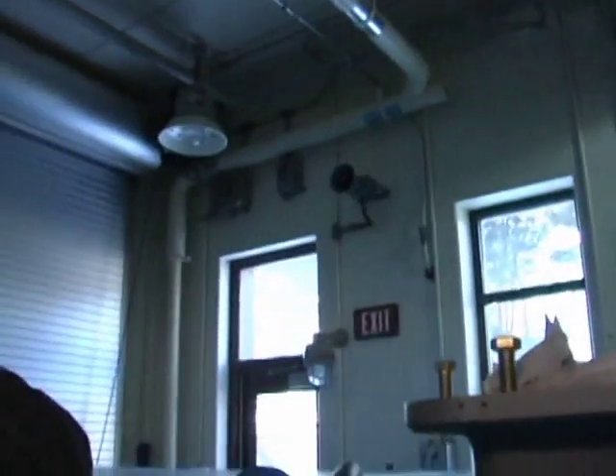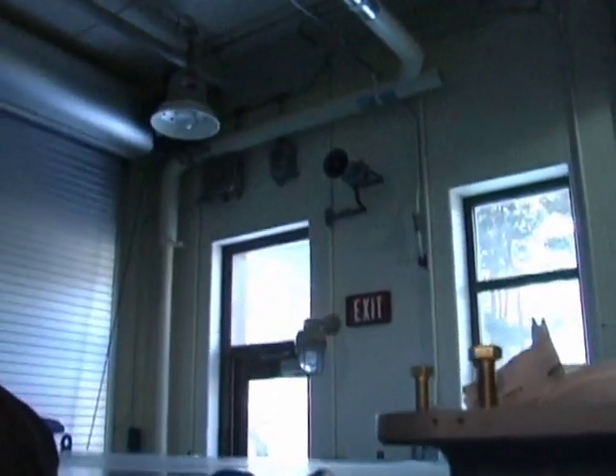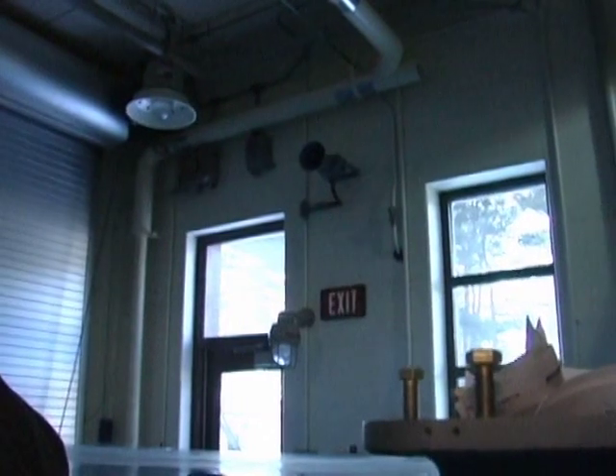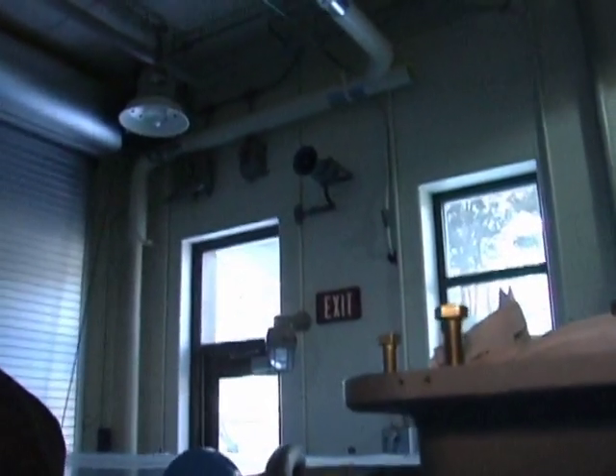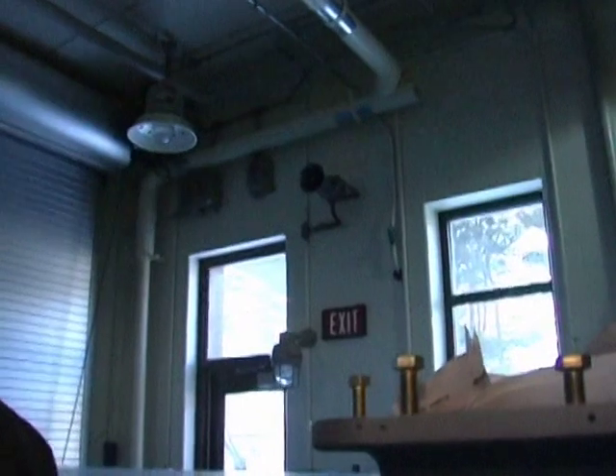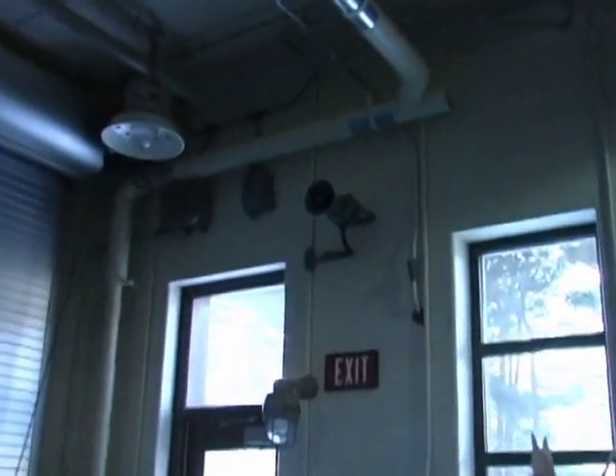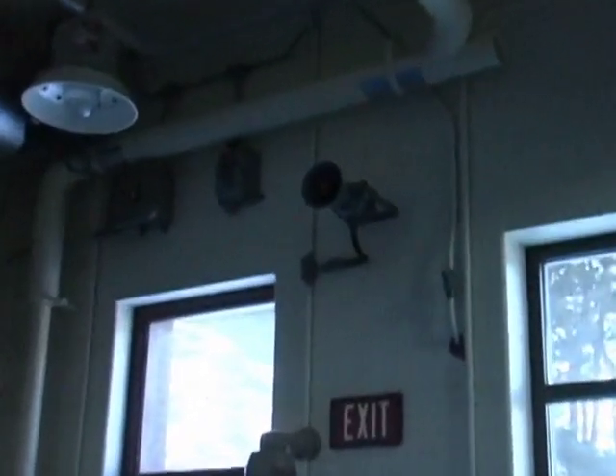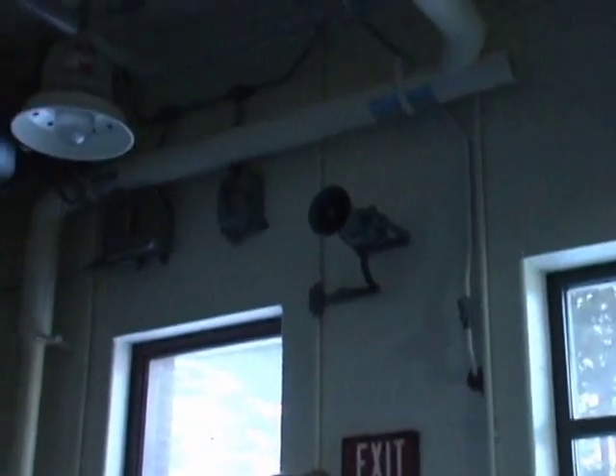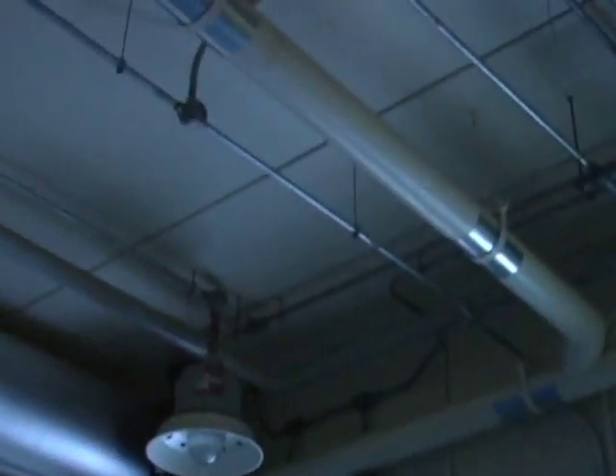The white beacons near the door and on the other side of the room there are the fire alarm indicators. There's also a speaker system associated with that, so you get both a visual as well as an audible alarm in the case of a fire, whether it be a smoke detector or a heat detector. Up near the ceiling, there are several heat detectors. In this case, there's one over each container, so if you do get into a situation where you've got a high heat condition, that will be indicated through your fire detection system.